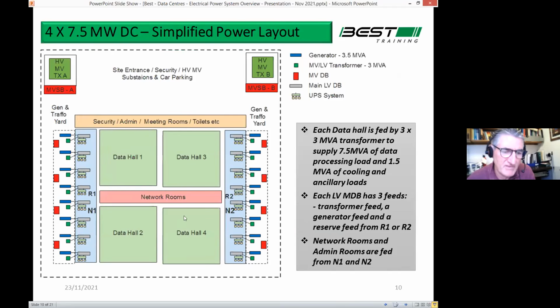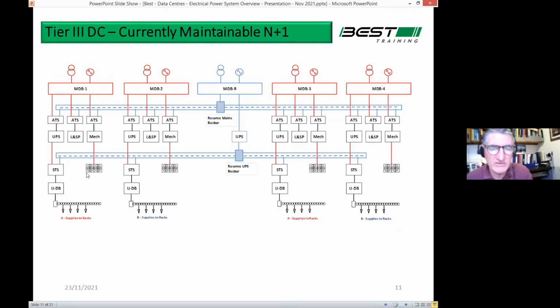Okay, 4 data halls, and each data hall has 3 transformers, 3 generators, and then in the middle you have a reserve. So if any one of these transformers or generators fails, the system is designed so they can pick up power, they can take power off the reserve system here. And we'll look at that in a few slides, I think. Next one. I didn't realize it was coming up so quickly.